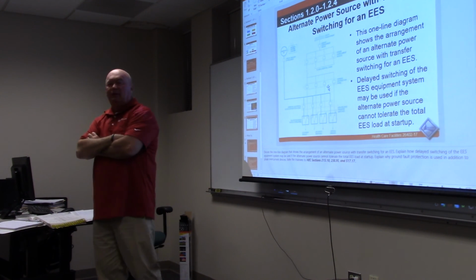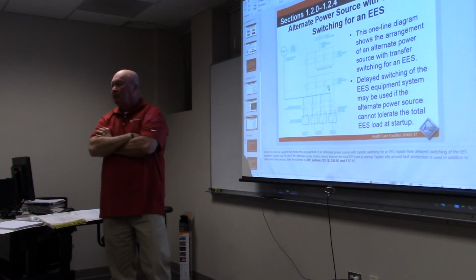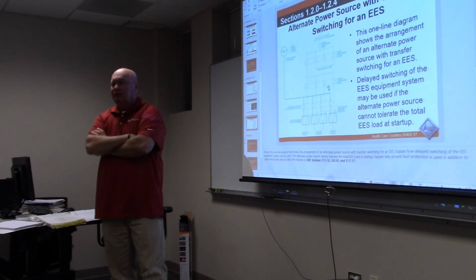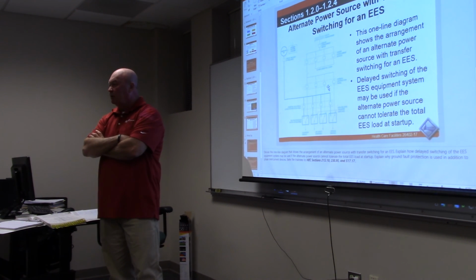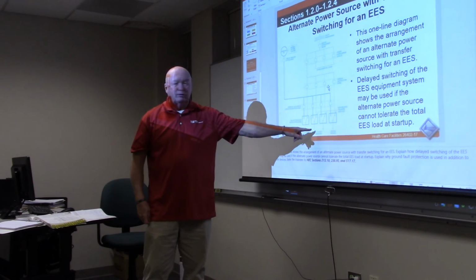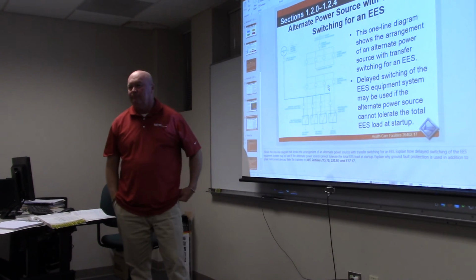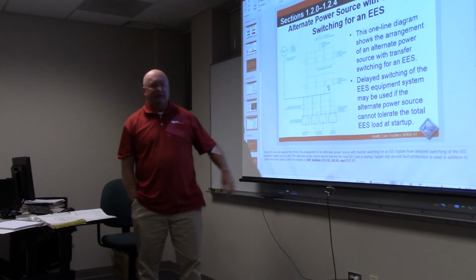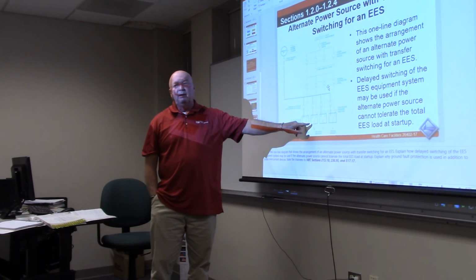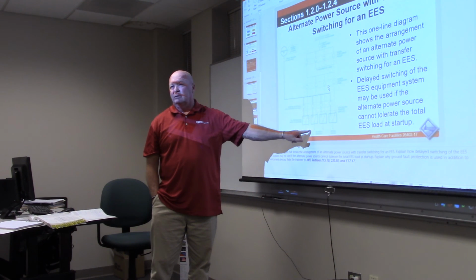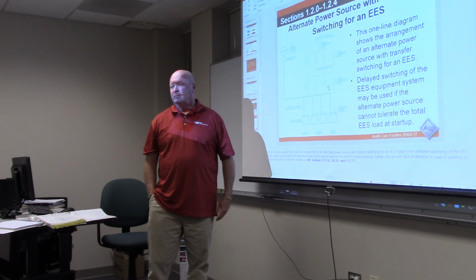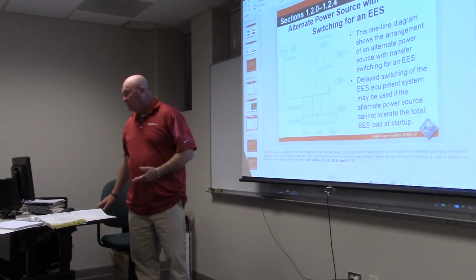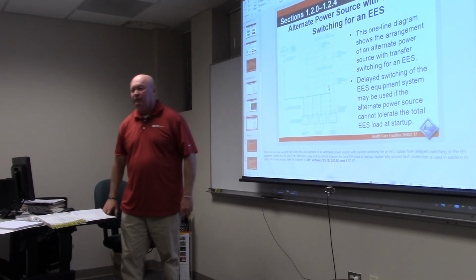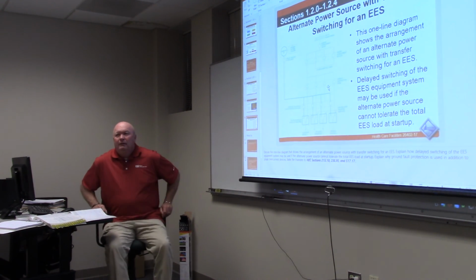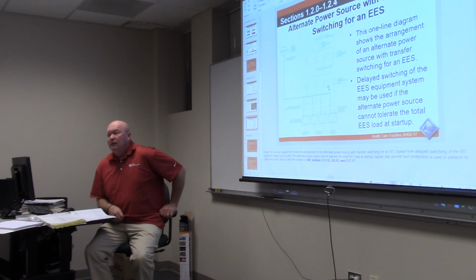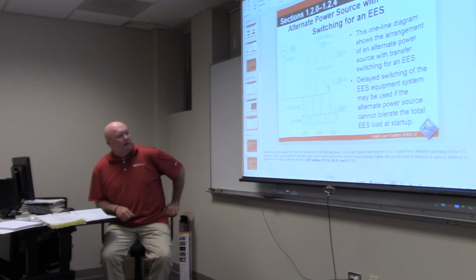Lighting—what would equipment be? Computers. Is that critical to get out of the building? No, so it's on a different switch than the life safety, isn't it? That's kind of overlooked sometimes, but it is a requirement in NEC that life safety be on a separate transfer switch than the equipment branch.